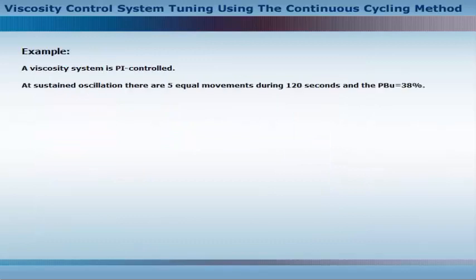Example: A viscosity system is PI-controlled. At sustained oscillation, there are five equal movements during 120 seconds, and the ultimate proportional band equals 38%. What are the settings on the PI controller?